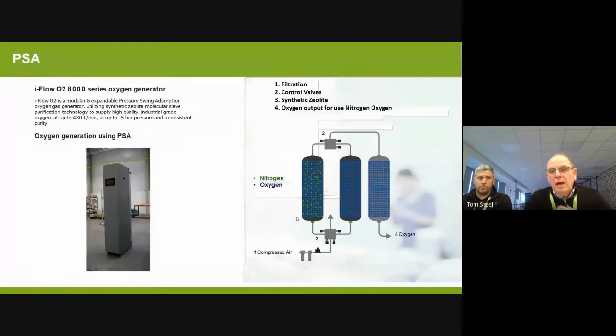So here we are. That would be a typical setup. You see your air coming in. What we have at the bottom there is a 5-3 valve that will either direct the incoming air to pressurize the tank, and it will allow the other tank to be depressurized and vent out the nitrogen. The pure oxygen is then carried over into a receiver tank, and that then can go out to whatever application we are using.